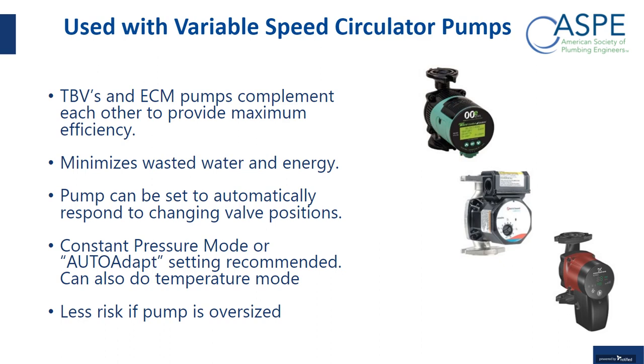Under a constant pressure mode, as I described the operation before of a thermostatic balancing valve, as the valves start getting satisfied, they start closing. As the valves start closing, you're going to start seeing an increase in pressure across the pump. When the pump is in a constant pressure mode, that will be the signal to the pump to start slowing down the RPMs of that pump to maintain a constant pressure. So it's really a great way.